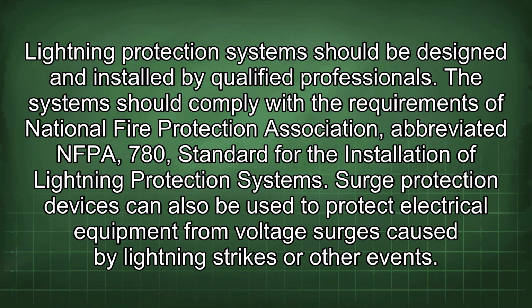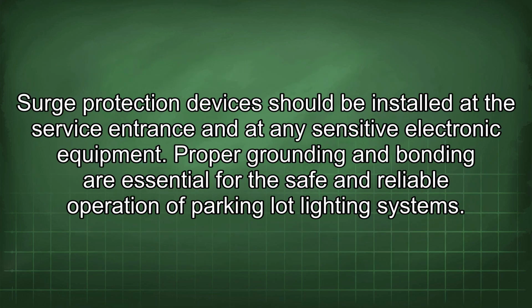The systems should comply with the requirements of National Fire Protection Association, abbreviated NFPA 780, standard for the installation of lightning protection systems. Surge protection devices can also be used to protect electrical equipment from voltage surges caused by lightning strikes or other events. Surge protection devices should be installed at the service entrance and at any sensitive electronic equipment.